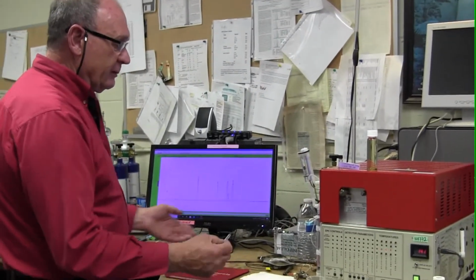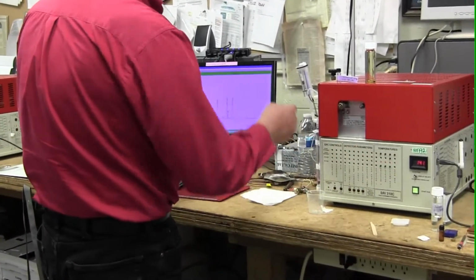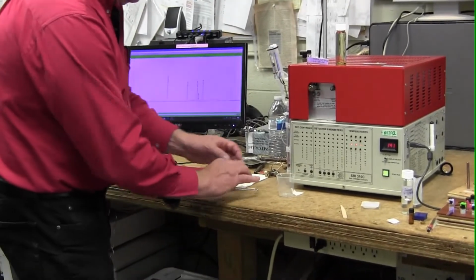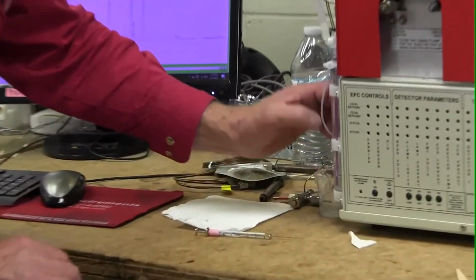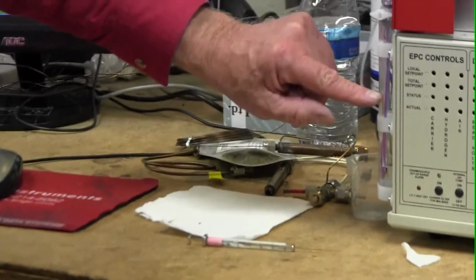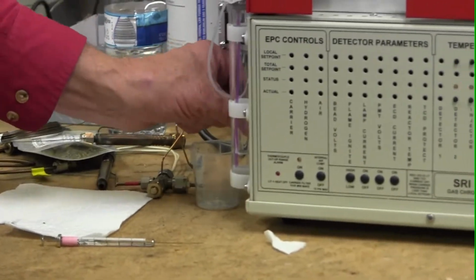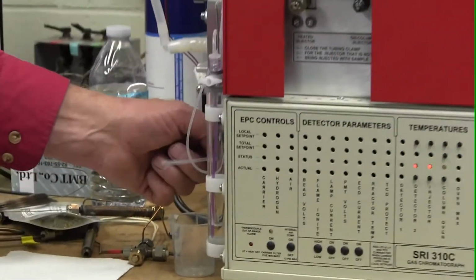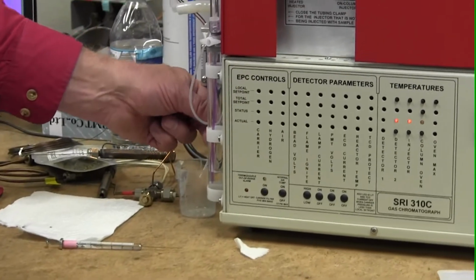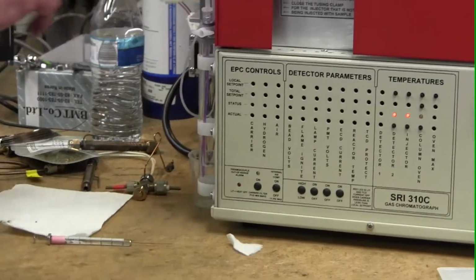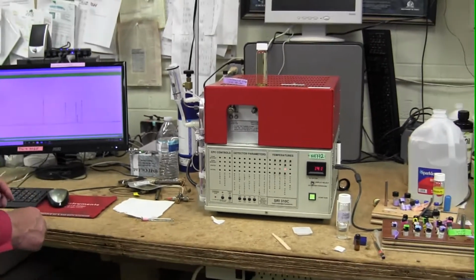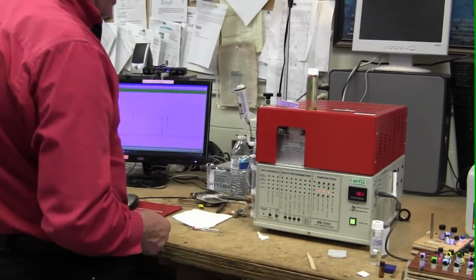So the way you do this, in the morning you come in, you just make sure you're filled with water here. You make sure that you've emptied the water trap. If the water trap is more than half full, then empty the water trap by turning this little valve, and all the water will spurt out this tube. We'll do that later so you can see it. I don't want to do it right now because you have to wait a few minutes after you do that for everything to kind of build back up.